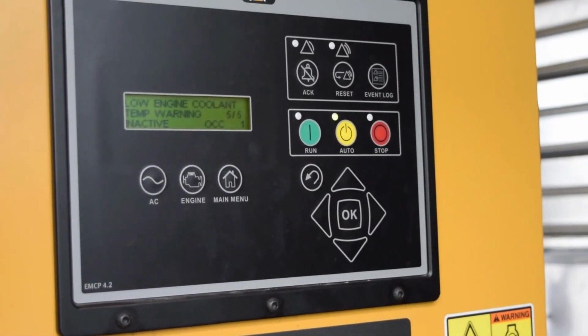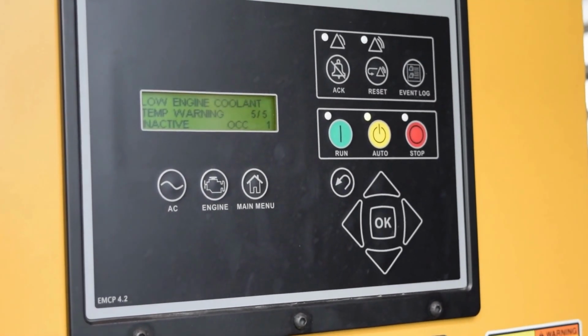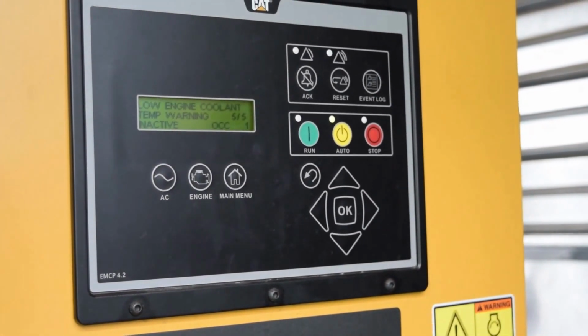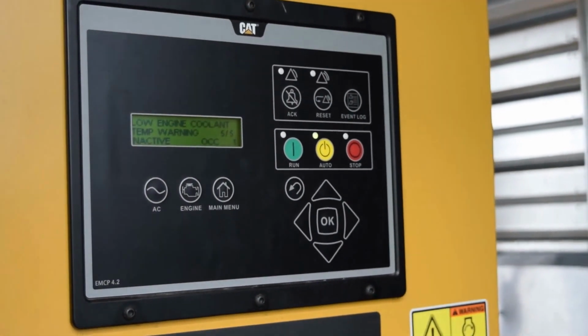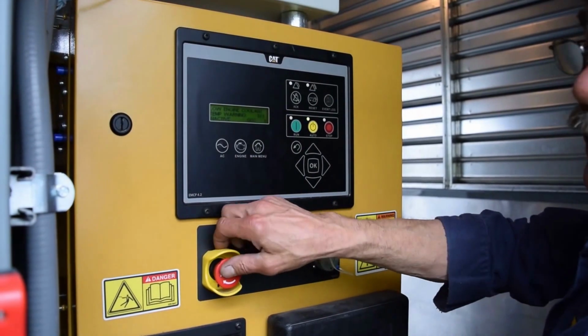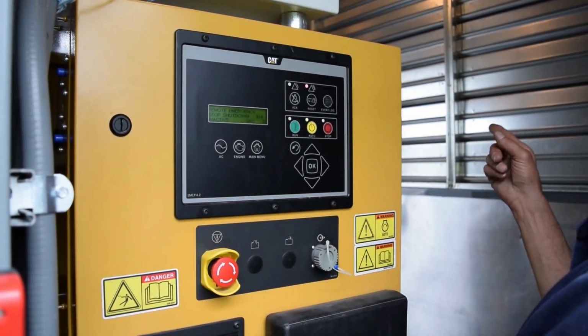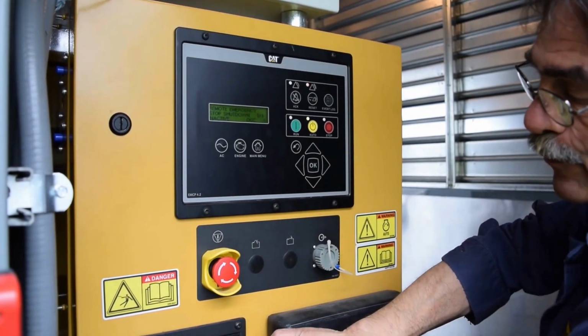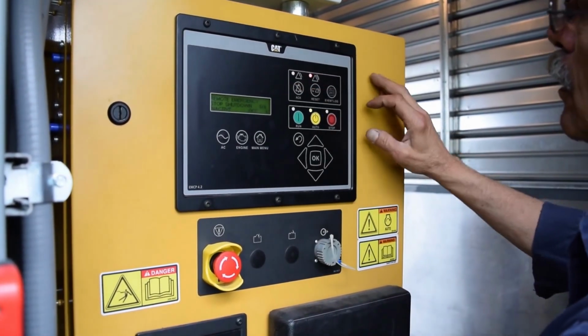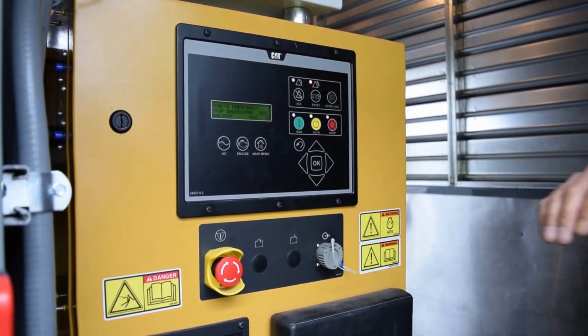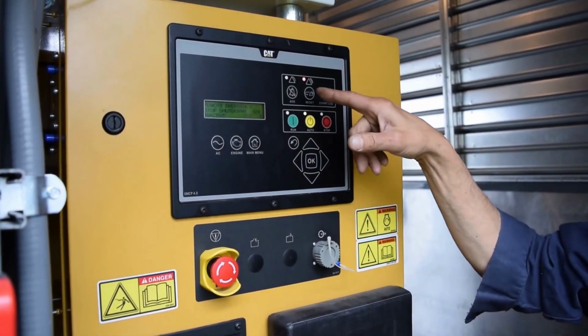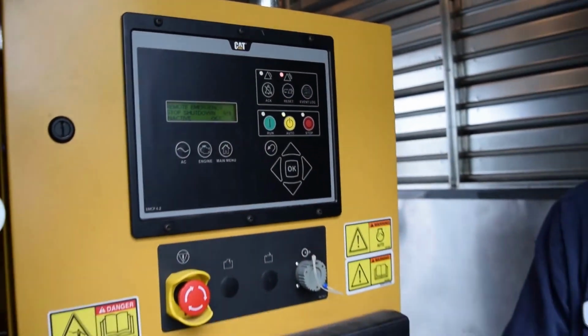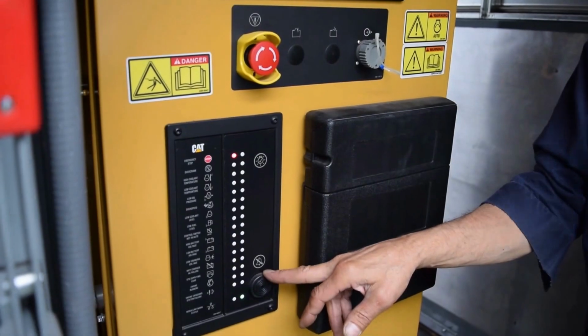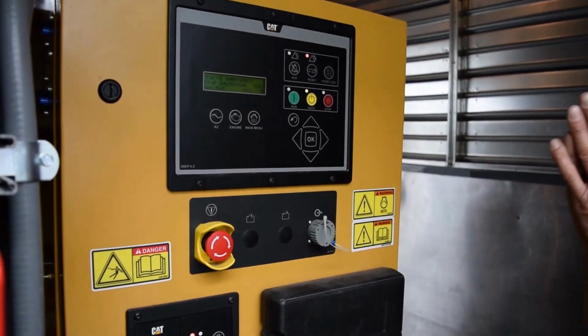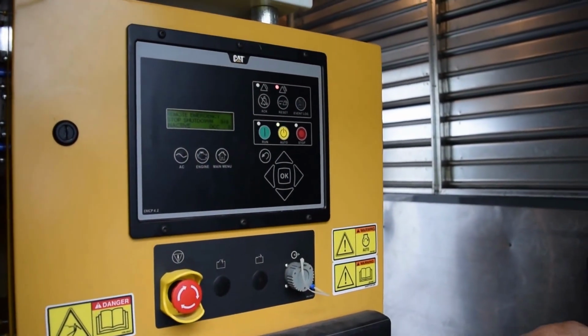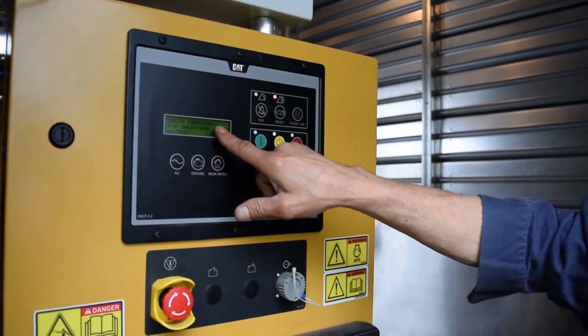We were talking before about tripping breakers, so I guess now is actually a pretty good time to find out what happens, because I want to show you how to reset a fault, because it's very important. I'm just going to silence the horn while I do this, but we're going to e-stop the engine, and the breaker just tripped. As you can hear, we have an audible, and I silenced it with the acknowledge. If that alarm comes in and I hit this acknowledge button, or the one downstairs, it will stop all the alarms. It's a global acknowledge. But as you can see now, I have a red light and I'm locked up, I'm shut down.